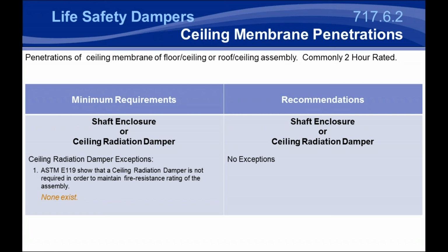Now, this doesn't extend to dampers alone. This extends to all the components of the floor ceiling or roof ceiling design. As you look through the Fire Resistance Directory, you'll see hundreds of different types of assemblies, and some are very restrictive and very prescriptive, and some are more loosely operating. Basically, the main takeaway is knowing all of the insulation, gypsum, and damper allowances, because we'd hate to have contractors or inspectors call up that have a certain floor ceiling or roof ceiling assembly with penetrations where they're not allowed. That's when knowing what's allowed in the ceiling membrane is required.